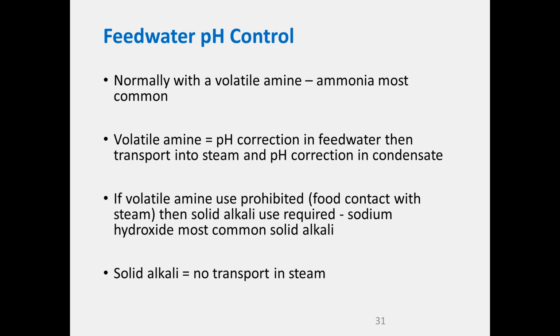But again, it depends on your plant, depends on whether you've got direct contact. If you've got non-contact heat exchangers, so that you have the process being heated on one side and the steam condensing on the other, then ammonia is normally your best choice because it works quite well. And it's easy, and there's a lot of science being done around its use.